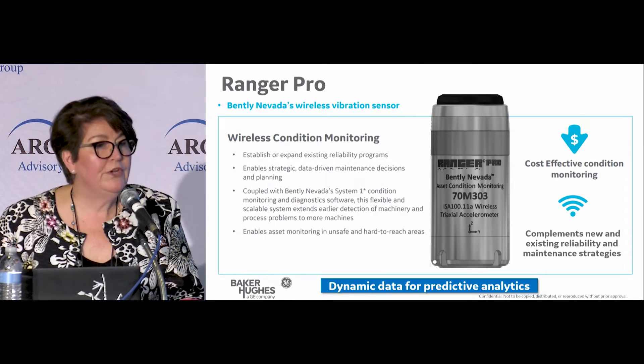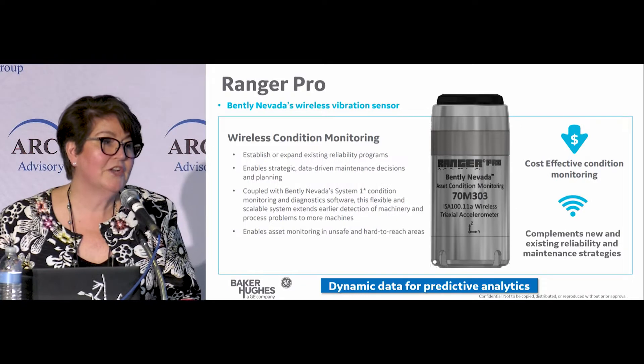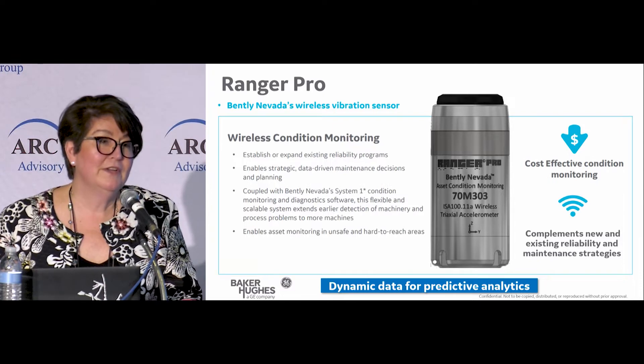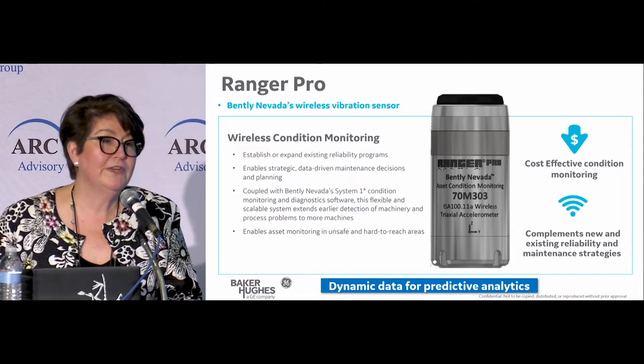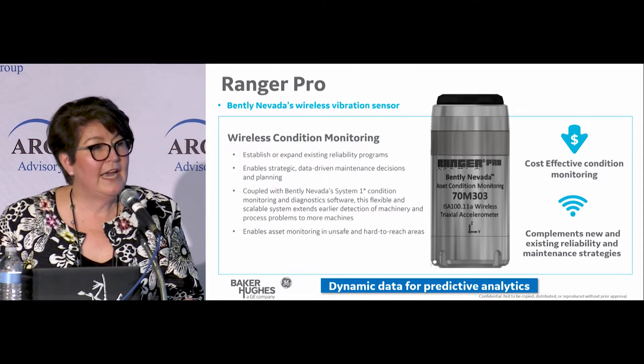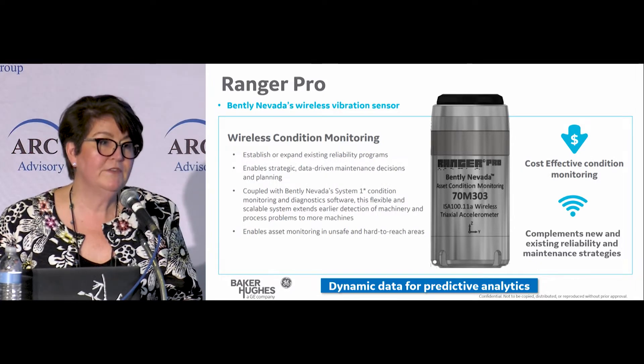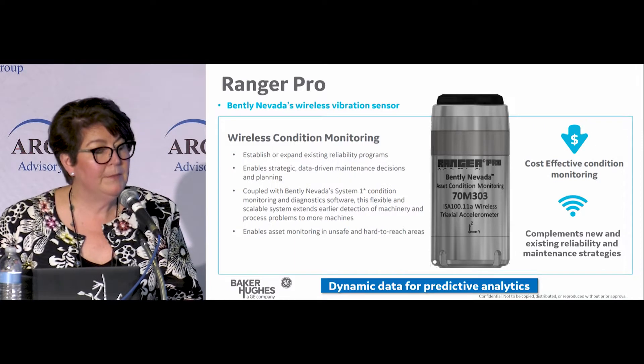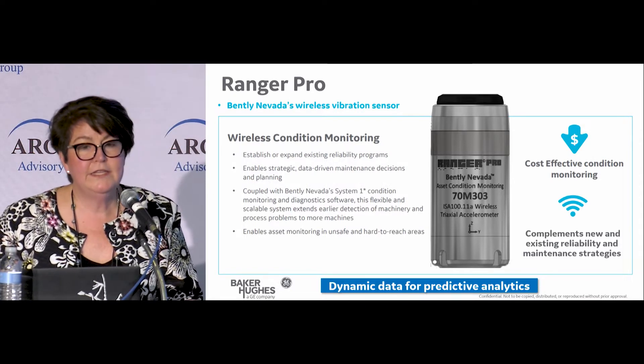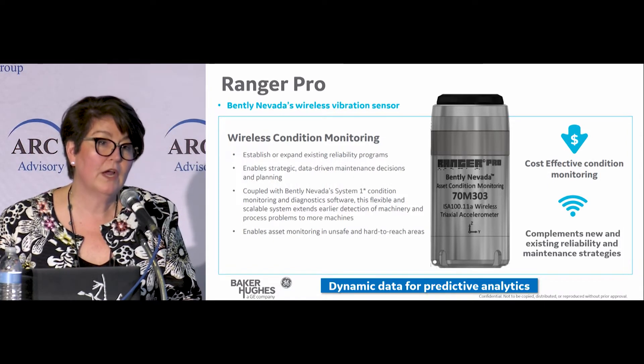Ranger Pro is actually very unique. When you think about Bently Nevada products, this is a zone zero device. It has a range of roughly 200 meters — about two football fields. It has a lithium D battery, which is kind of unique in the industry. When you think about shipping devices and batteries globally, the fact that it's a lithium D battery means it can be easily sourced locally. Even with getting data every 10 minutes, it has three to five years of battery life for our customers.